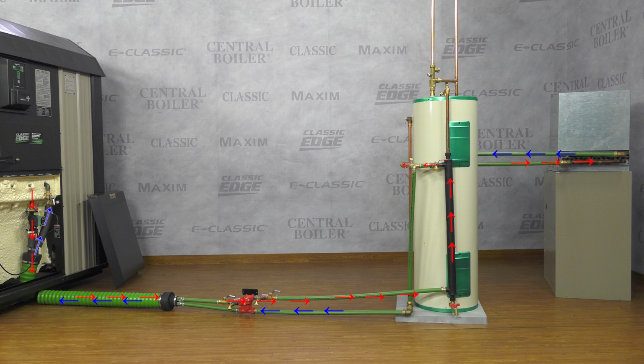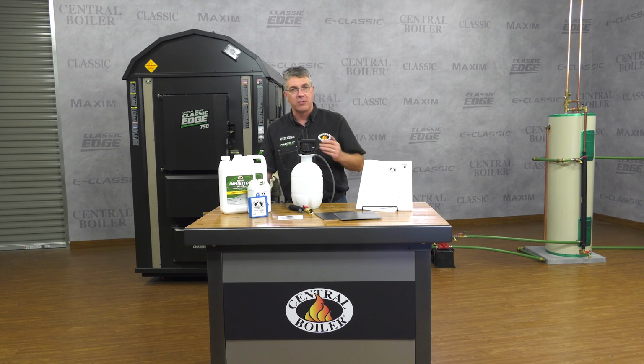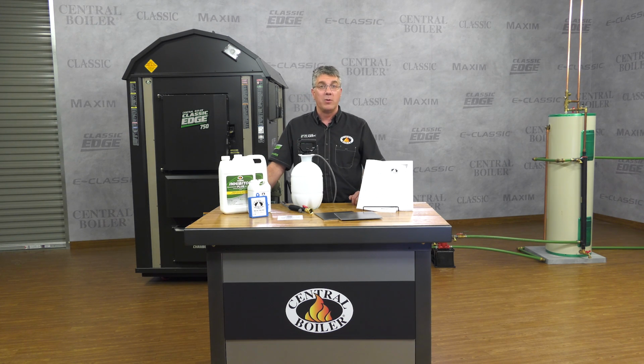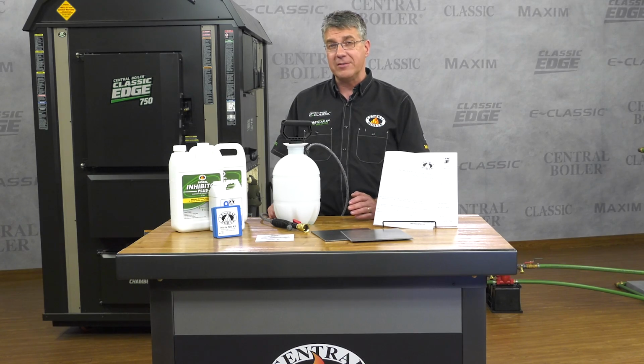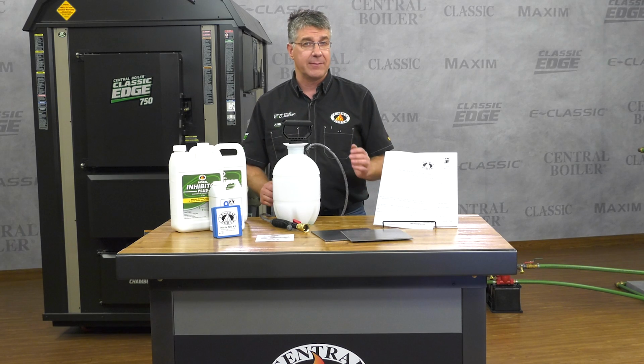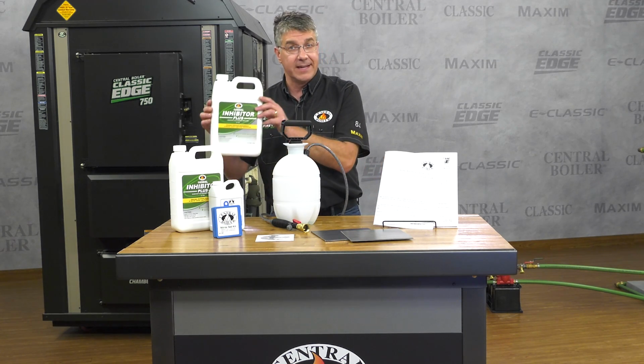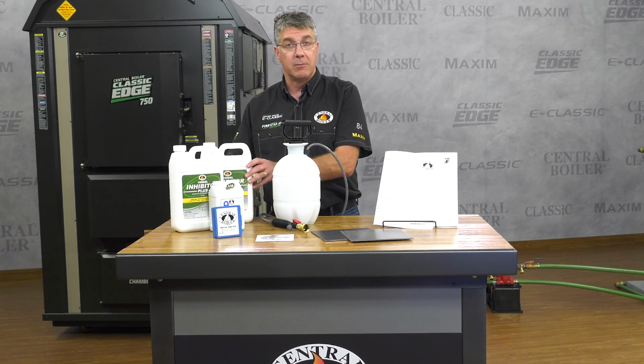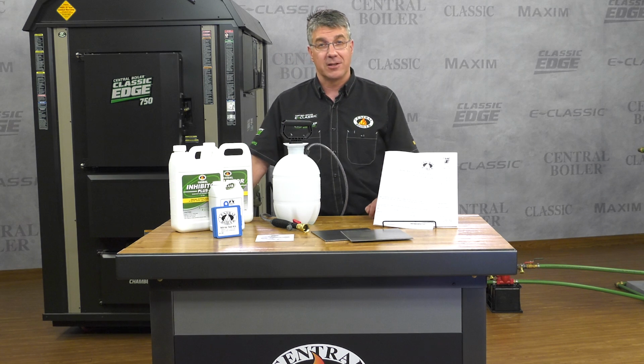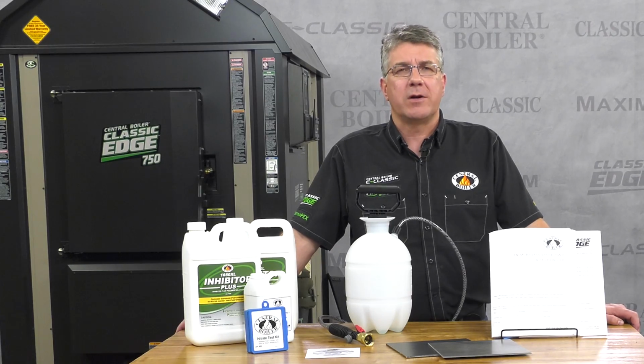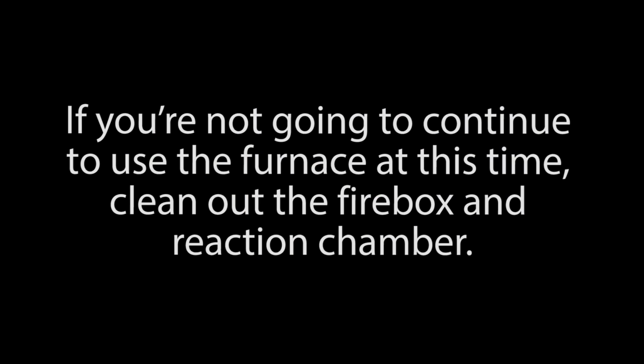Now that we've added the Corrosion Inhibitor Plus, the MolyBoost, the water, and purged the system, we need to heat up the water. Now the reason we need to heat up the water is because there are certain types of microbes that may want to eat the nitrites in the corrosion inhibitor. When we heat the water up, we kill those little bugs. After you heat up the water to operating temperature, if you're not going to continue to use the furnace at this time, clean out the firebox and reaction chamber.